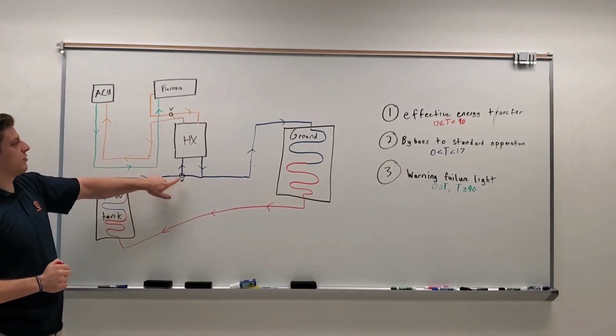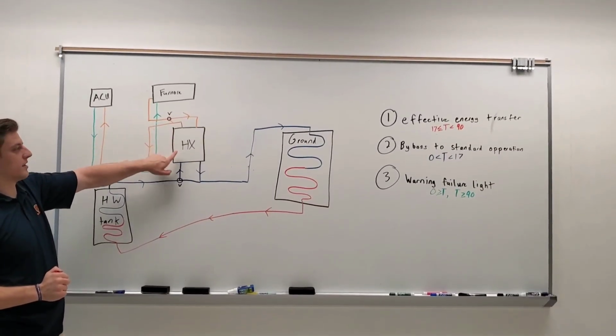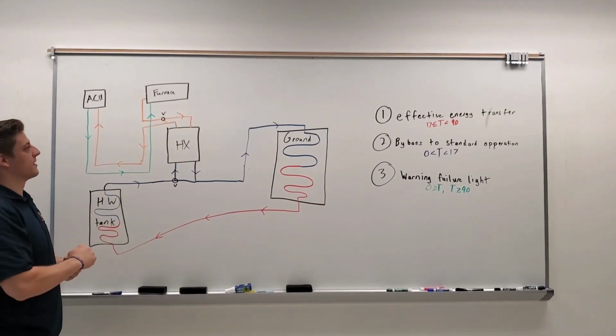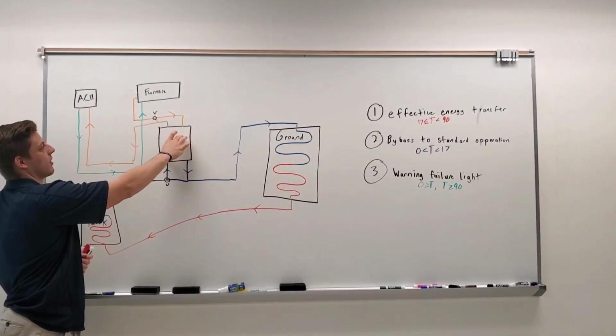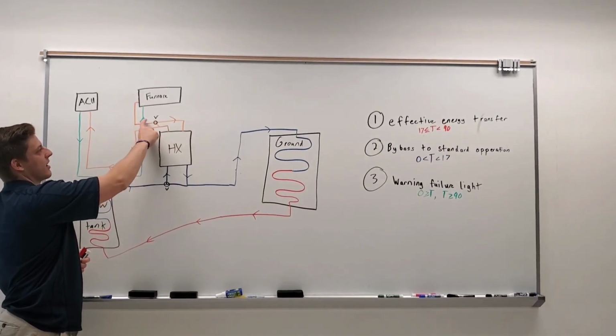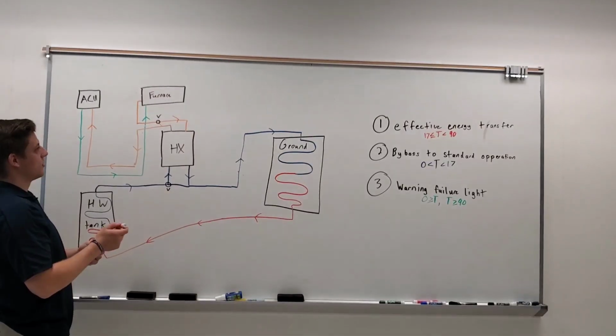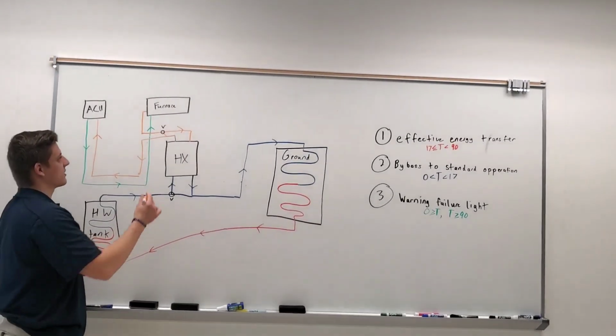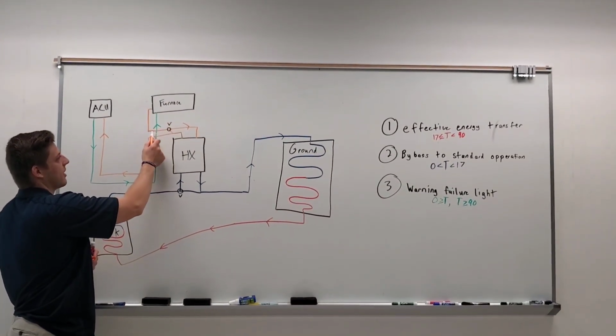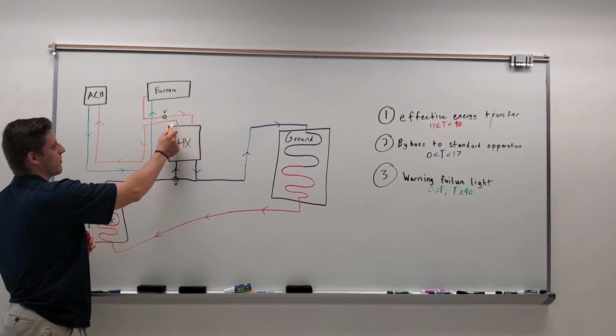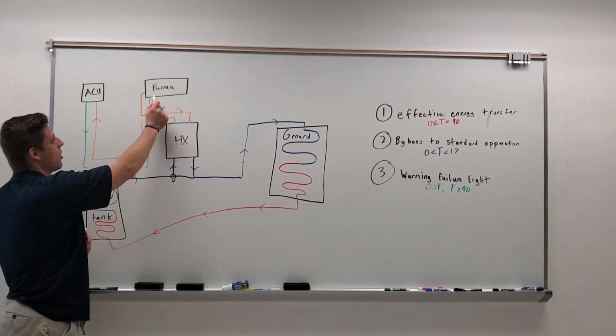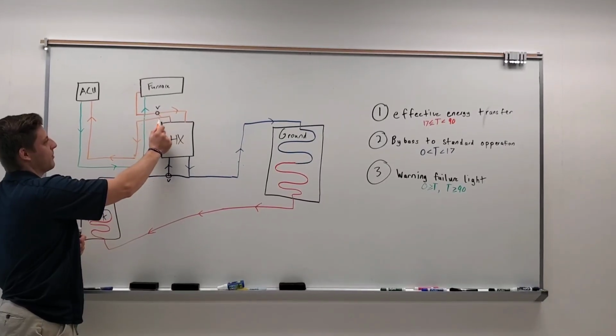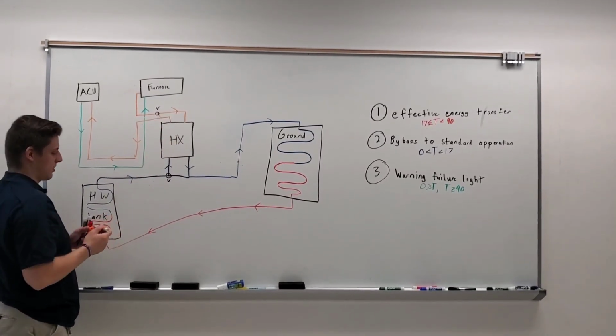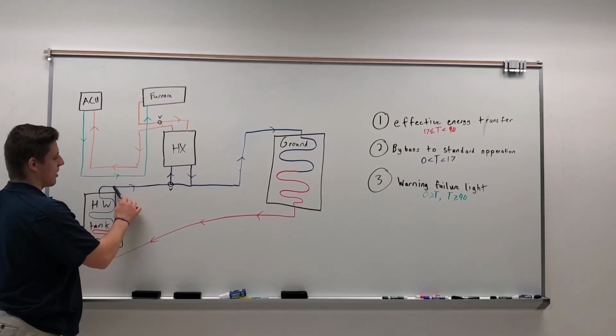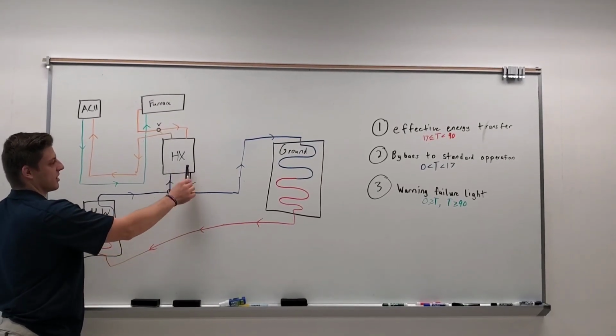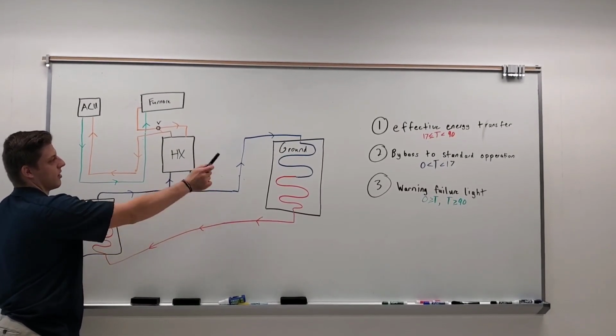However, we need to add two different valves on the supply side of this heat exchanger. The reason why is if the heat exchanger is ineffective to run, we have a bypass valve, so that it can just run as a normal loop. So our two paths for each are: the warm refrigerant coming out, down, over, into the heat exchanger, and back out after transferring some of its heat and continuing, or out, down, over, bypass the heat exchanger and continue on a normal loop. The same is done for the domestic water. It can either come through, up to the heat exchanger and out, or just go straight through on its regular loop.